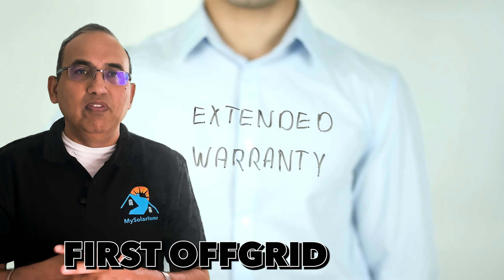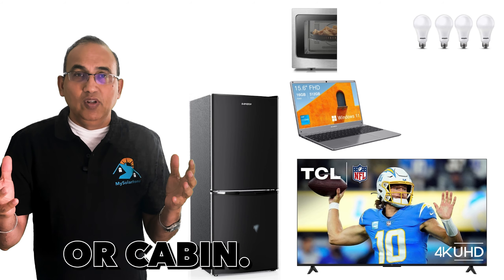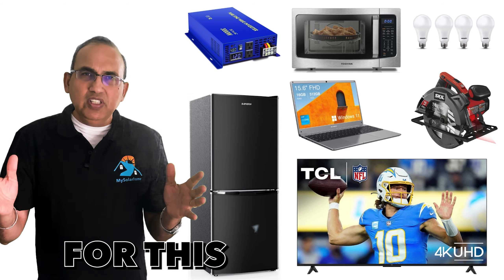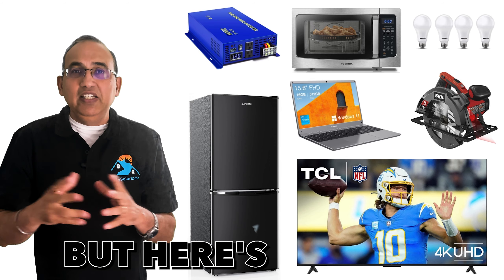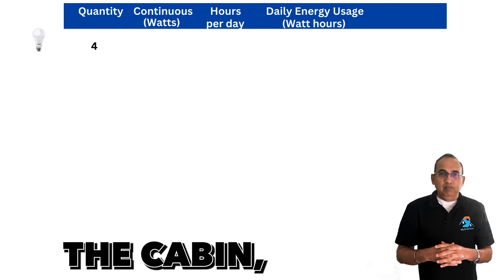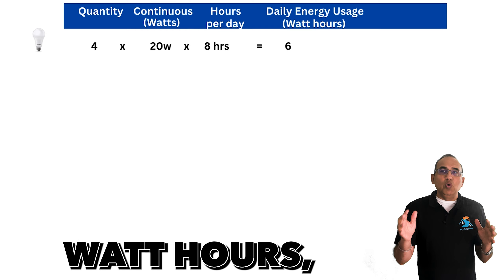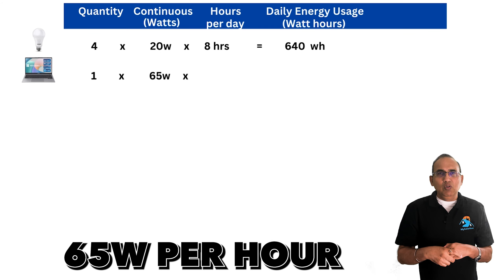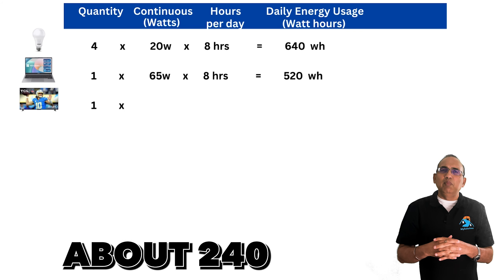The first step is to figure out the energy requirement for your home or cabin — what will be powered and how much energy is needed every day. I have a consumption calculator link below. For our cabin today: four LED lights at 20 watts each running eight hours a day gives 640 watt-hours. A laptop running eight hours at 65 watts gives 520 watt-hours. A 40-inch TV for four hours at 60 watts requires about 240 watt-hours.